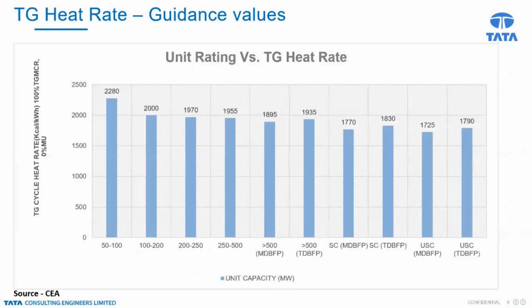If you see the evolution of the thermal power sector in India, I talked about 150 megawatts started in the 1960s. Before that, we started implementing smaller capacity units; 50 megawatt and 67 megawatt were also standard sizes we had earlier. From 50, we gradually increased the unit rating to higher capacities. Mainly, we got the heat rate improvement from that increased unit rating. When we go for increased unit rating, we obviously increase the steam parameters, both pressure and temperature.